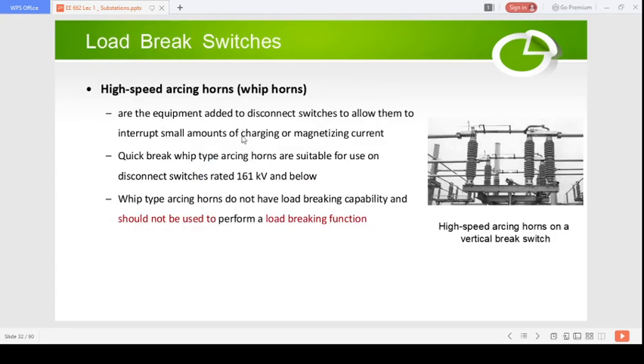There is a special type of arcing horn called the high speed arcing horn, or what we call the whip horns. These are equipment added to disconnect switches to allow them to interrupt a small amount of charging or magnetizing current. The quick break whip type arcing horns are suitable for use on disconnect switches rated 161 kV and below. So these quick speed arcing horns are specifically used only at 161 kV or below voltages.